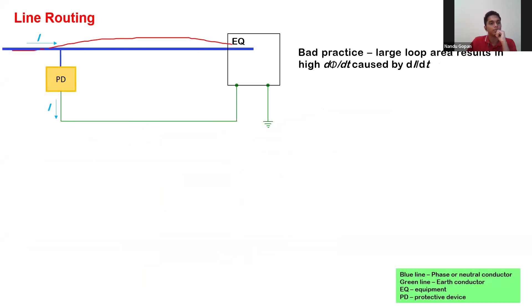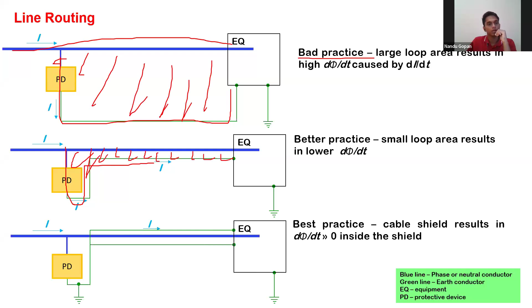Here's another example of line shielding. Suppose you have a line, this is the P conductor, and this is the SPD. In the standard, one arrangement is shown as bad practice - and I know in India, most places this is being done. The recommended practice, and the best practice you can get, is different: in case of any surges, the induced voltage will only be in a small area. In the bad arrangement, the induced voltage will be very large; in better arrangements it's progressively less. So this is the best line routing.